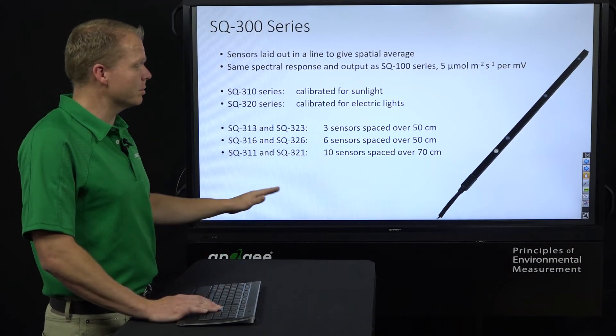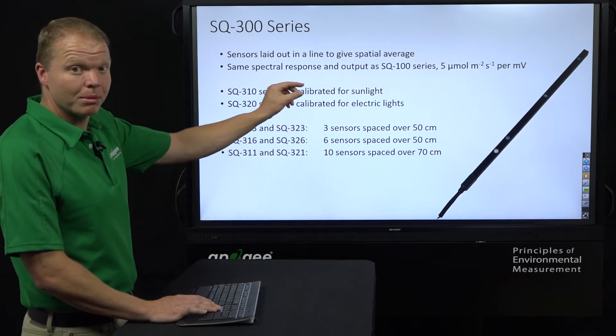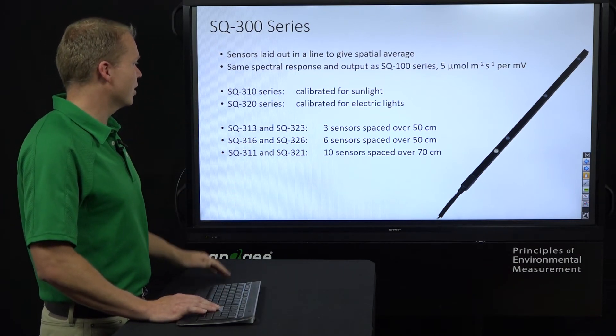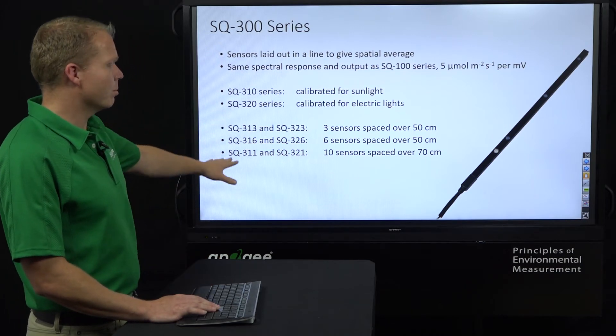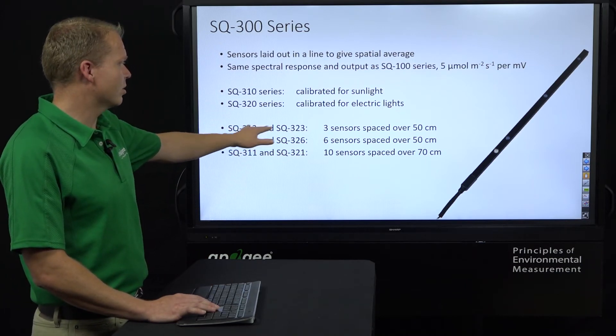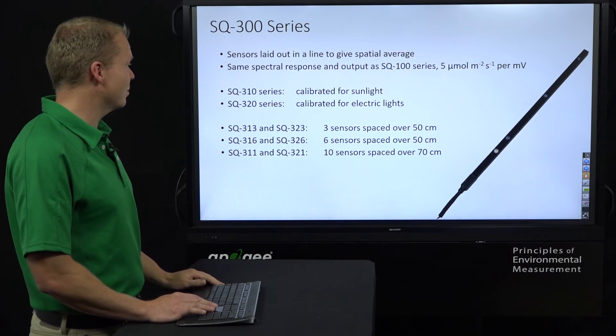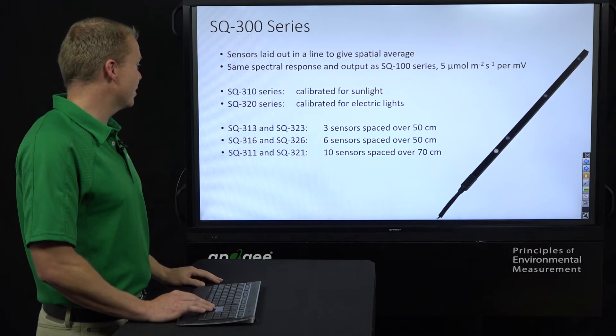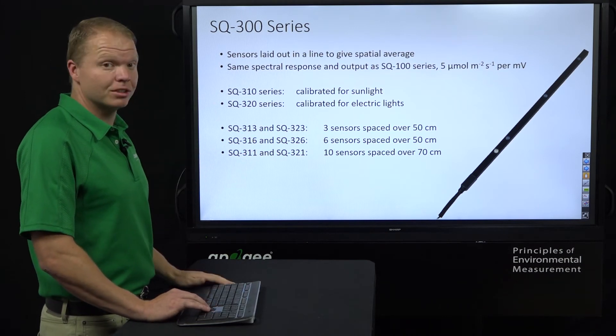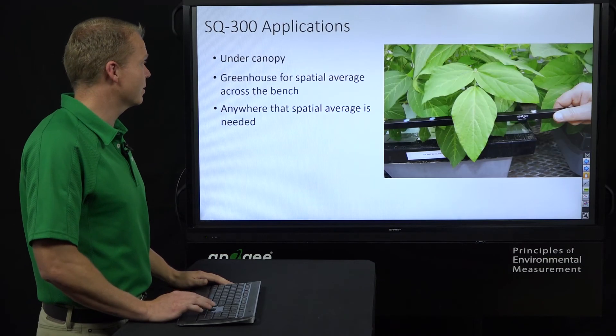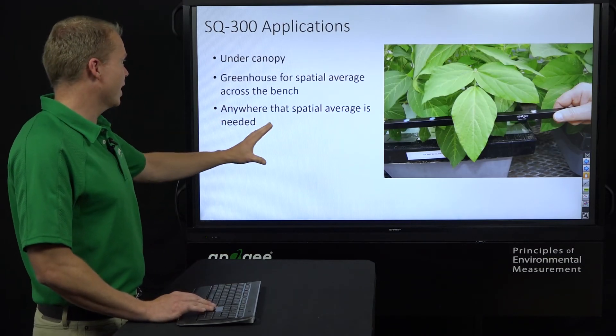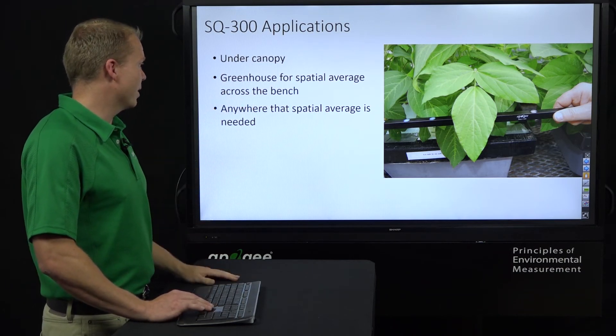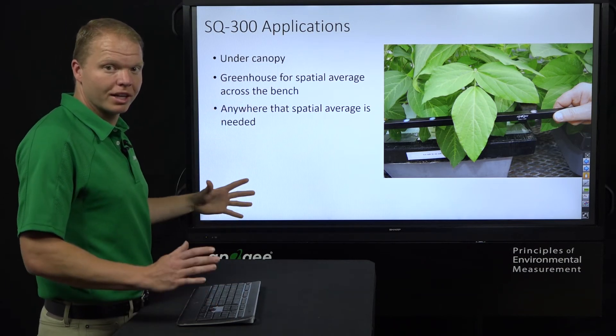The SQ300 has the same sensor as the 100 and 200 series, but placed in a light bar so you can get spatial averages. The 310 is for sunlight and the 320 for electric light. The 313 and 323 have 3 sensors spaced over 50 centimeters; the 316 and 326 have 6 sensors over 50 centimeters; and the 311 and 321 have 10 sensors spaced over 70 centimeters. You can use it under a canopy, on a bench, or anywhere you want that spatial average.